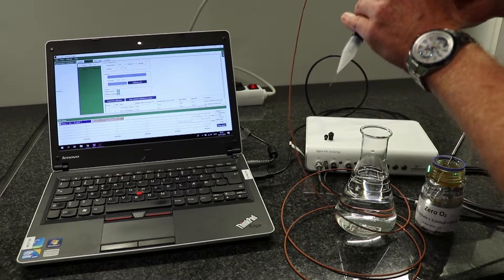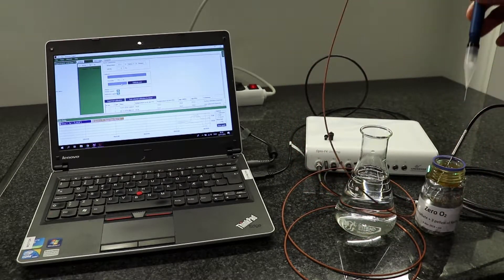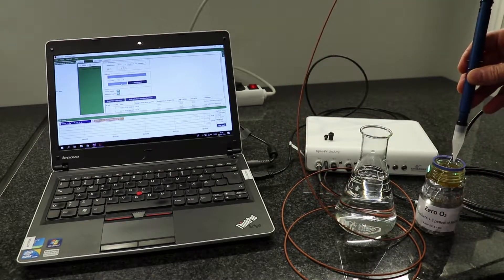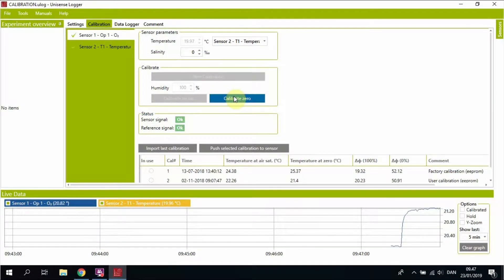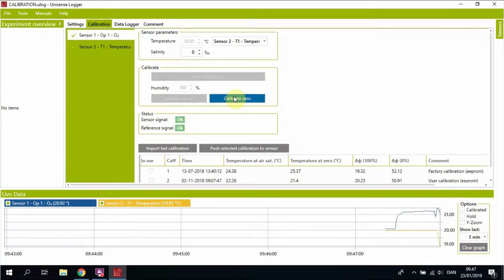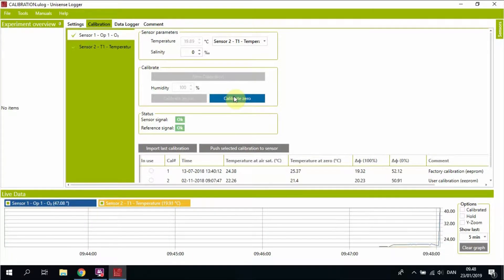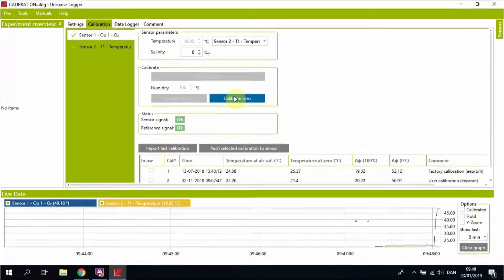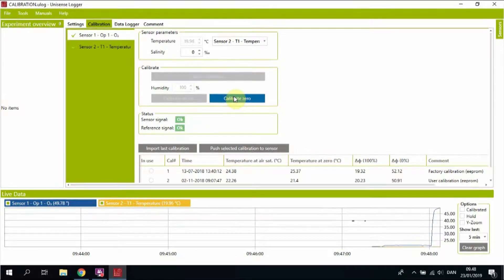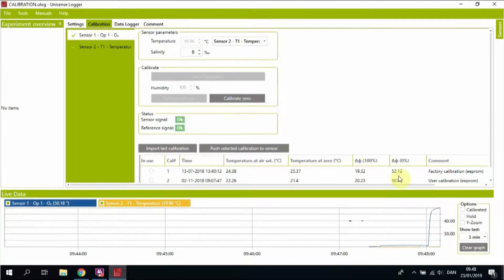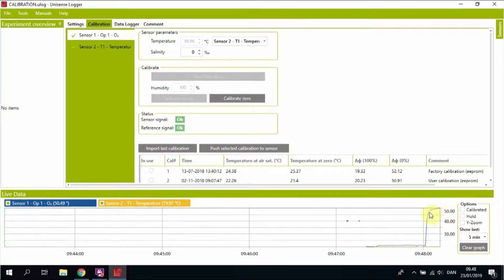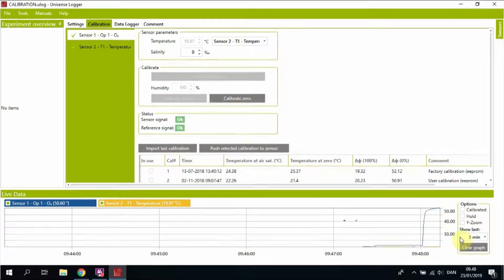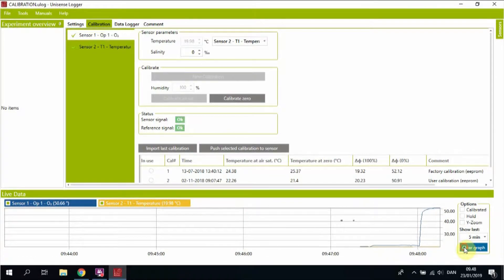Expose the fiber once more, still flashing with an orange light. Wait for the signal to become stable. You see the signal is actually increasing now. The value is somewhere between 45 and 55 for a good sensor.